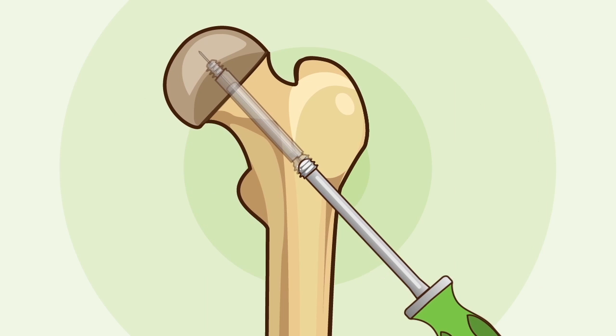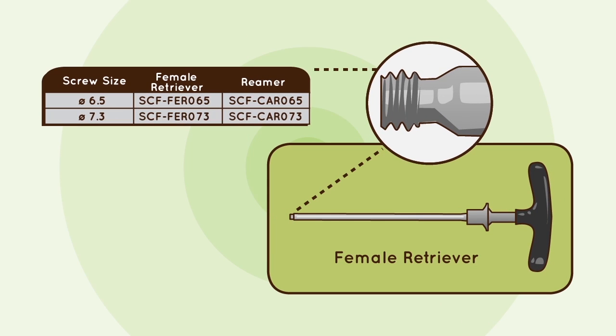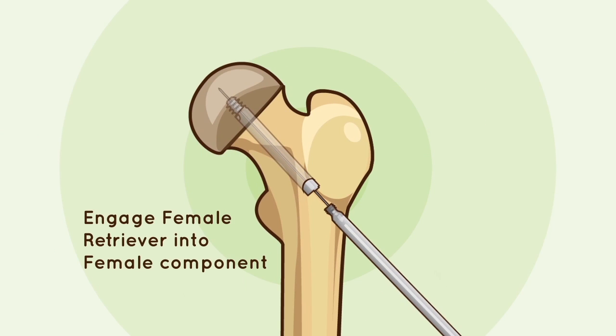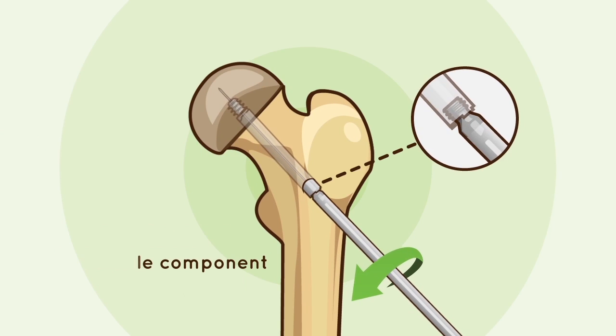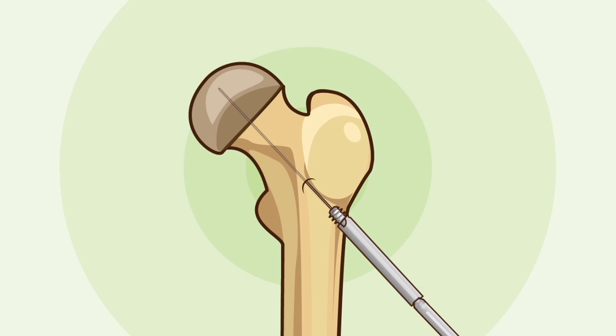Female component removal: Engage the female retriever corresponding to the implant size into the female component. Using a counterclockwise rotation, rotate while applying traction to remove the implant component.